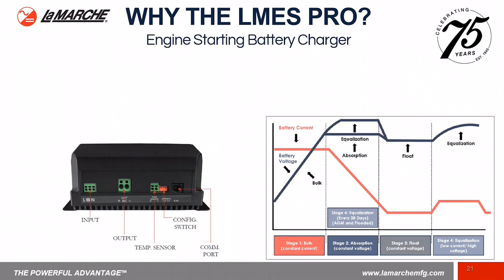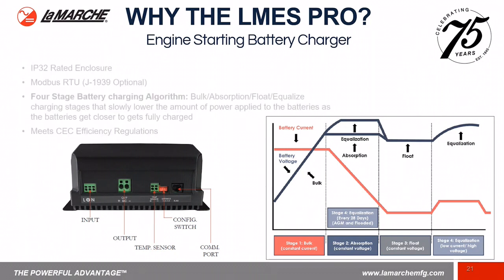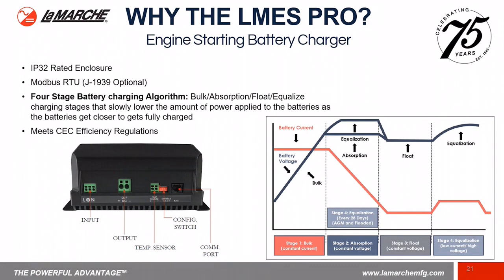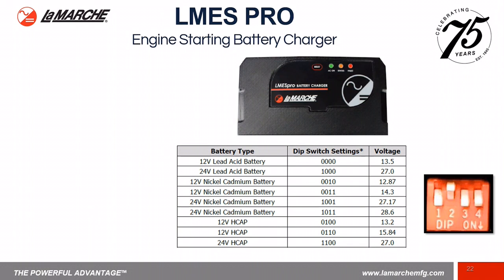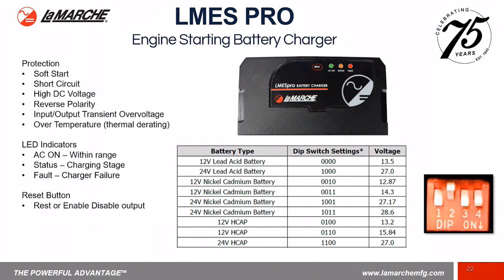The multi-stage charging system that we have on the LMES Pro is 4 stages: bulk, absorption, float, and equalize. The equalize is mainly for the lead acid or NiCad. The HCAP does not require an equalization. The LMES Pro also meets CEC efficiency requirements and is IP32 rated. It also provides reverse polarity protection, has a built-in monitoring system to monitor high voltage and short circuits, and has input and output transient voltage protection, along with over temperature derating.